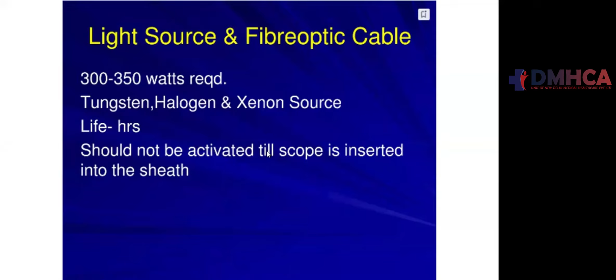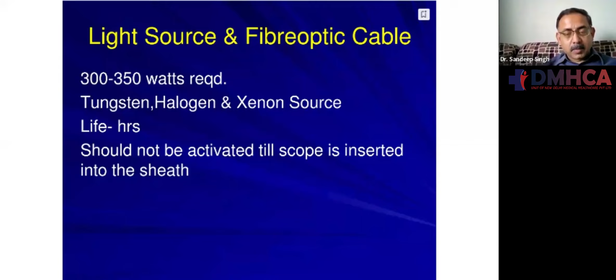Yeah. So then comes the light source and the fiber optic cable. The light source is typically 300 to 350 watt. That is the requirement. The light source can be a tungsten, halogen, or xenon source, and all these have different properties. In some respects one is better than the other, and sometimes the other is better. They all have a lifespan measured in hours. So these should only be activated when the scope is really inside the joint cavity, to protect the light source and to maximize its lifespan.